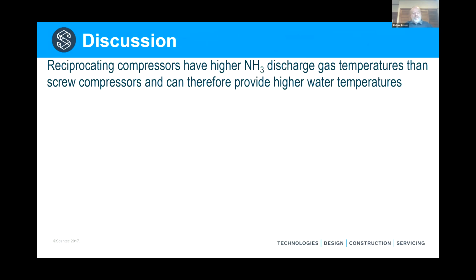And just some concluding remarks about reciprocating compressors versus screw compressors. We see discharge gas temperatures in reciprocating compressors from about 80 to 130 degrees, sometimes up to 150 degrees at part load. With screw compressors, it's much less. Oil-injected screw compressors, we see maybe 65 to 85, because a lot of the heat of compression is removed by the oil that's injected between the rotors. We can still recover that heat, but it is at a lower temperature. Typically, the oil temperature in a screw compressor is about maybe 50, 55 degrees entering the compressor, and 70 degrees or so entering the oil cooler.